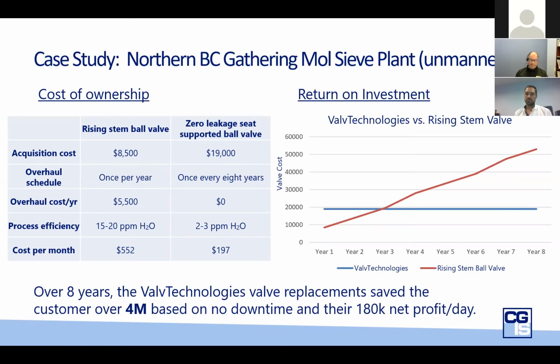We take that valve and we put it into a class 600 piping system where we're only running 900 or 1000 PSI, or 5500 to 6000 kPa, and we don't generate the same energy. But when we go into molecular sieve applications or dehydration applications, now we're dealing with a very low differential of pressure, typically less than 10 PSI or 15 kPa. And so we don't have the same energy being generated by the piping system to create energy and load on the ball and the seating system.